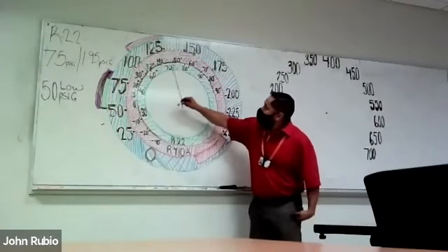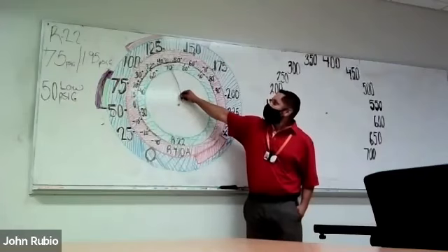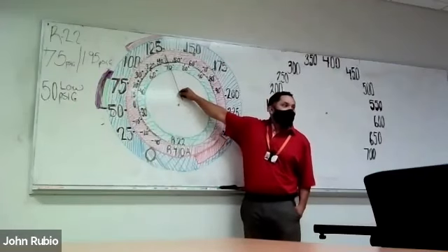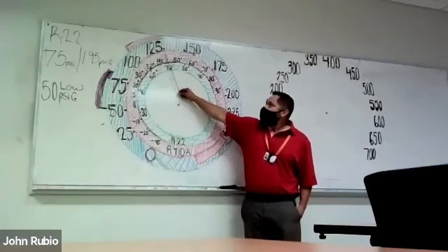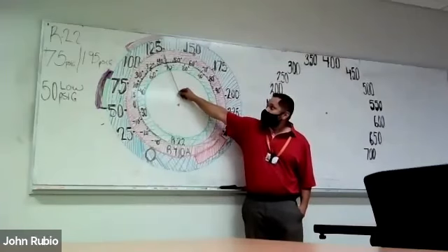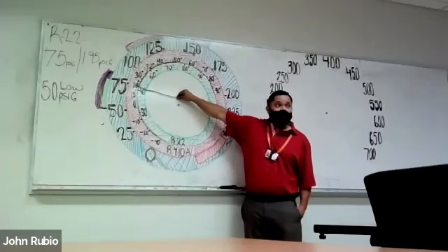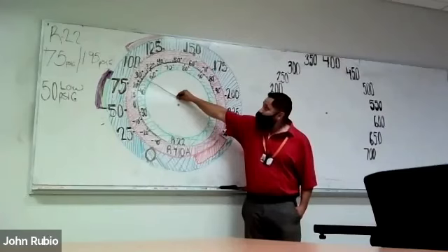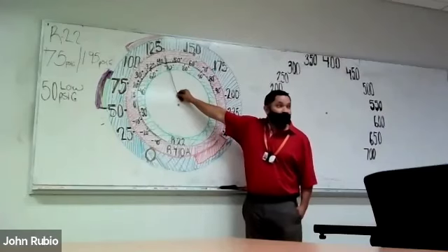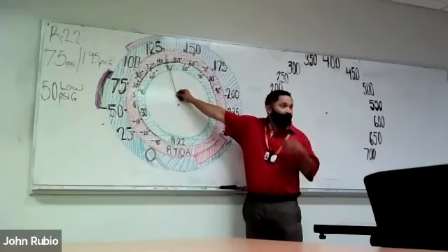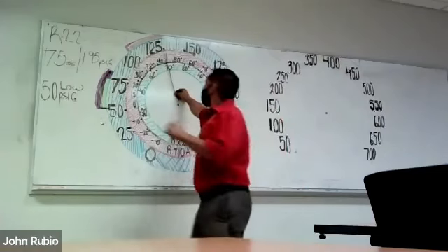So let's look here. Let's go with 410A. We're sitting here at 125, cruising. Can anyone tell me a similarity in the temperature between 125 cruising and the temperature when R22 is cruising, 42 degrees in the green bar, and then follow up in the pink bar to 42 degrees? Where do we wind up on PSIG? About 125 at 42 degrees.